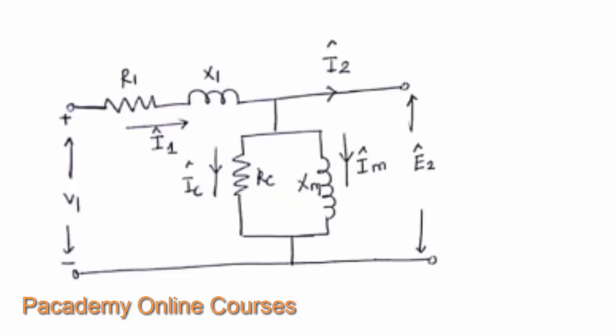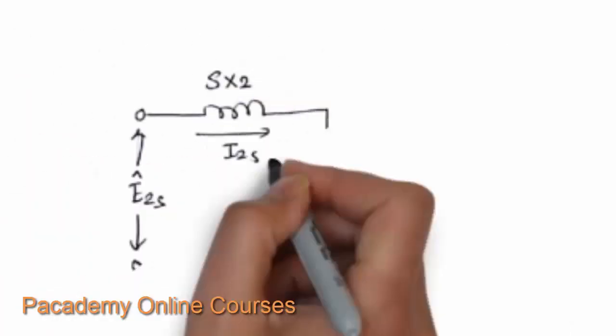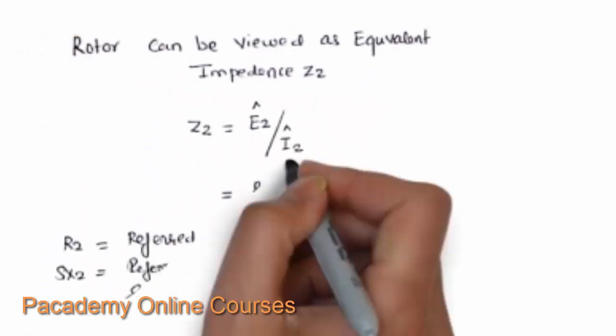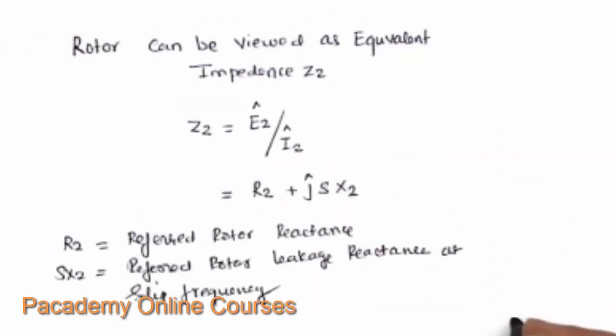I2 is the current flowing into the rotor and E2 is the voltage induced in the rotor circuit. The rotor circuit at running state has E2S as the induced voltage, SX2 as the rotor reactance, R2 as the rotor resistance, and I2S as the running-state current. The voltage induced in the rotor is S times the equivalent voltage available at the stator, since slip reduces the voltage by some amount.